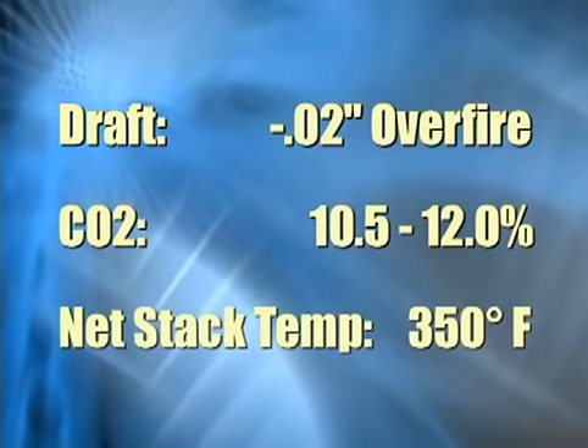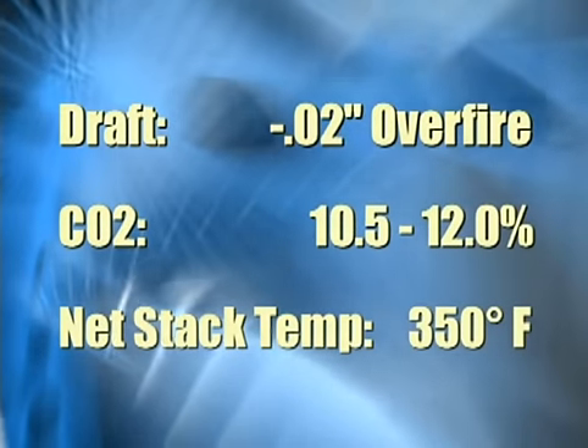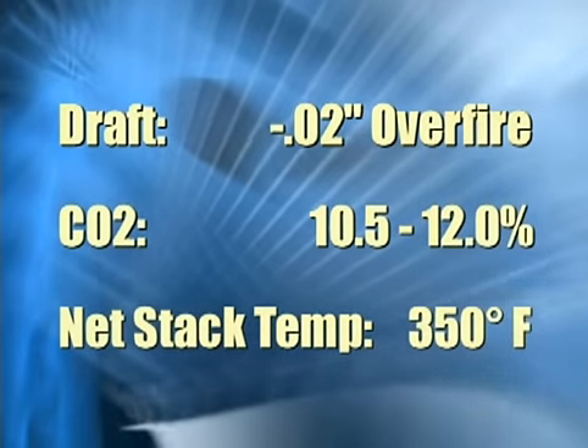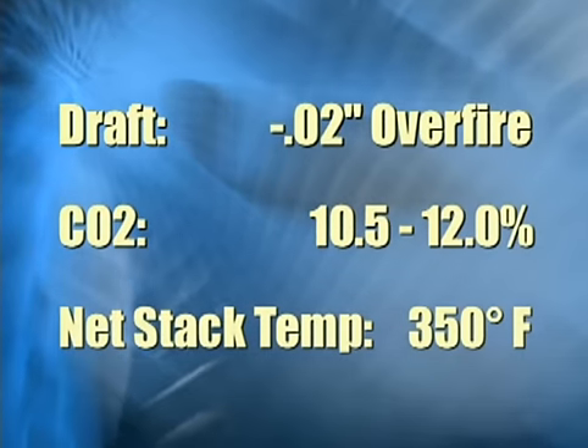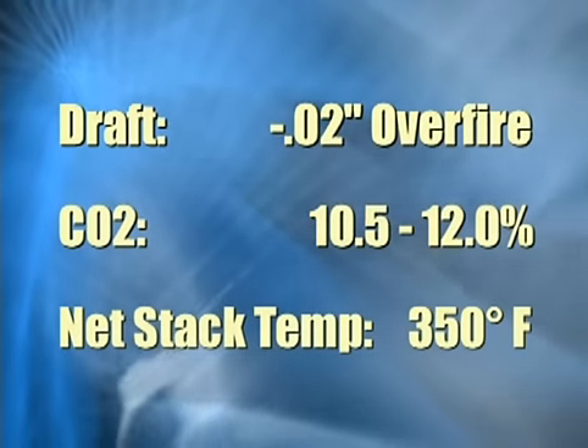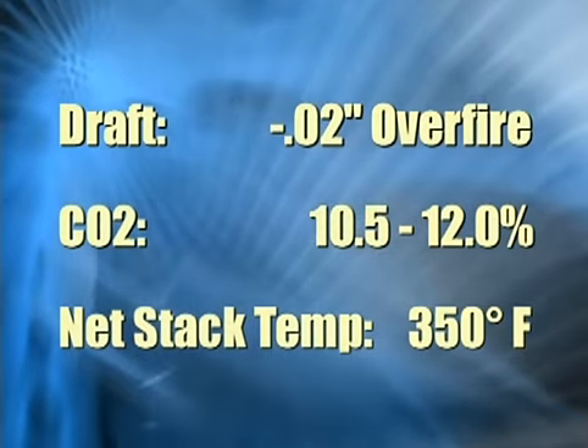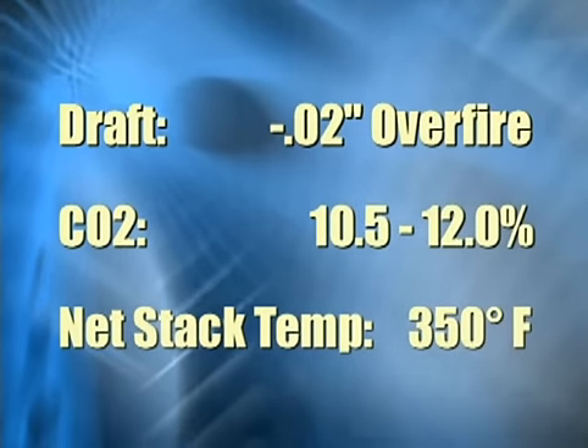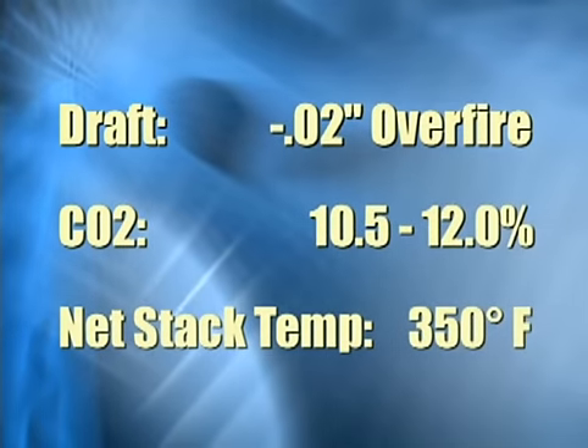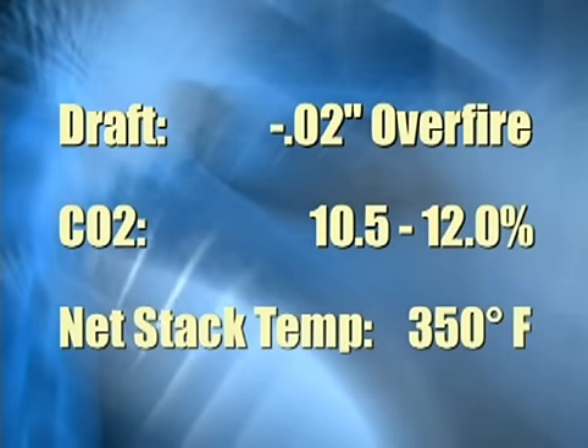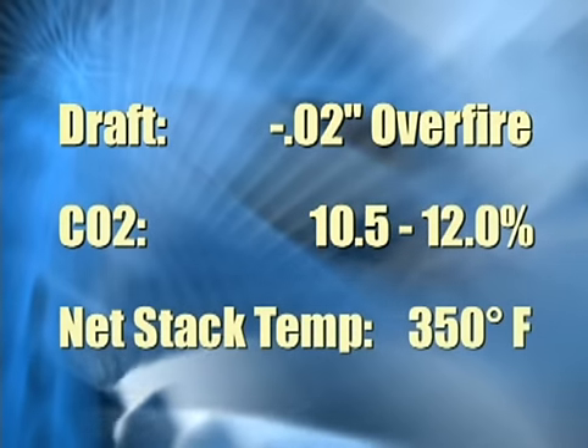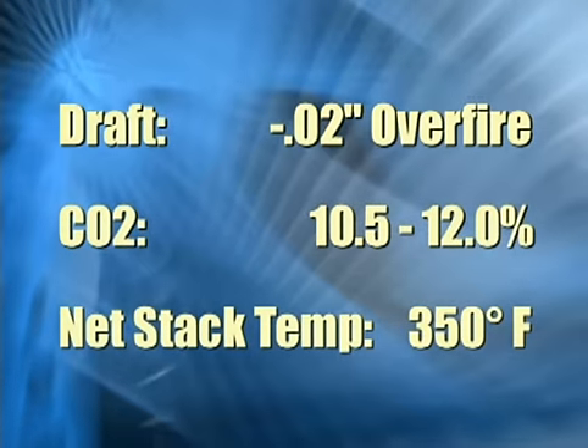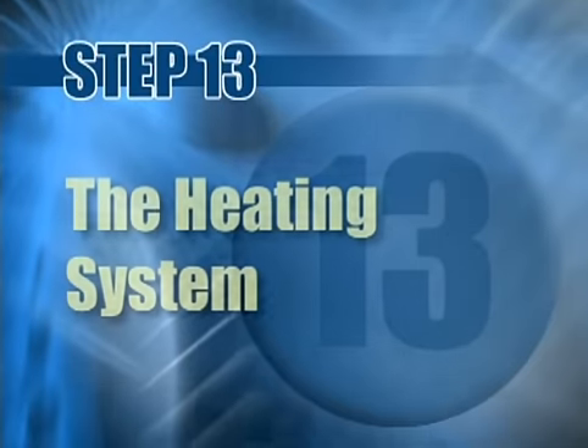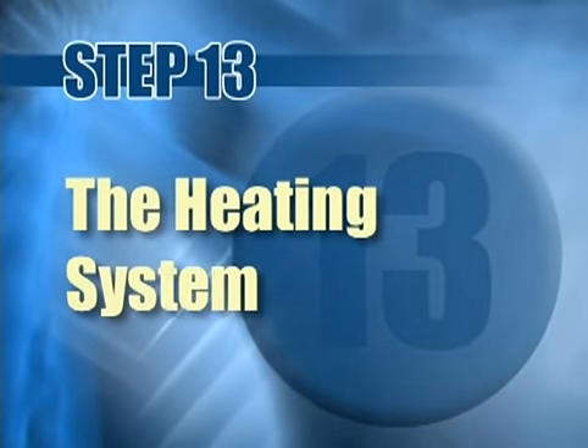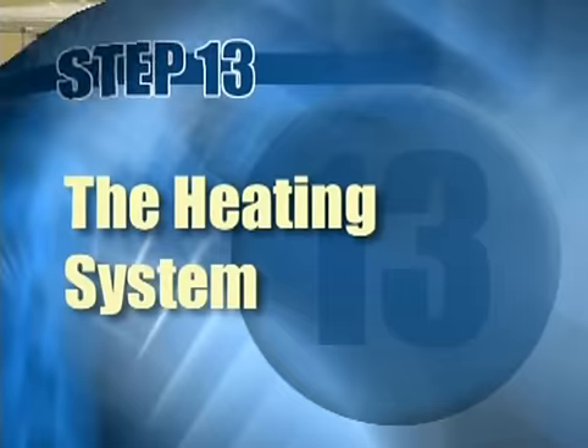Net stack temperature is an indicator of how well the heat exchanger is absorbing the heat produced by the fire. Under 350 degrees net, flue gases will condense, causing pipe and chimney corrosion. As a general rule, as long as net stack temperature is over 350 degrees Fahrenheit, the lower the temperature, the higher the efficiency. The following steps will vary depending on the type of heating system you're working on.